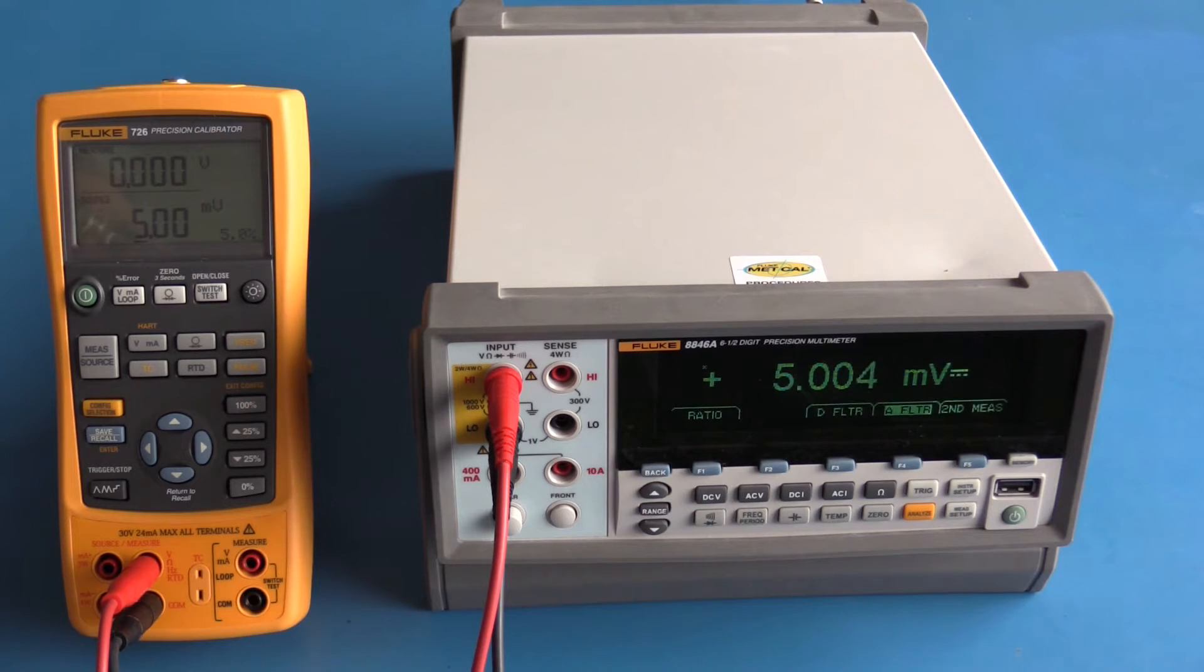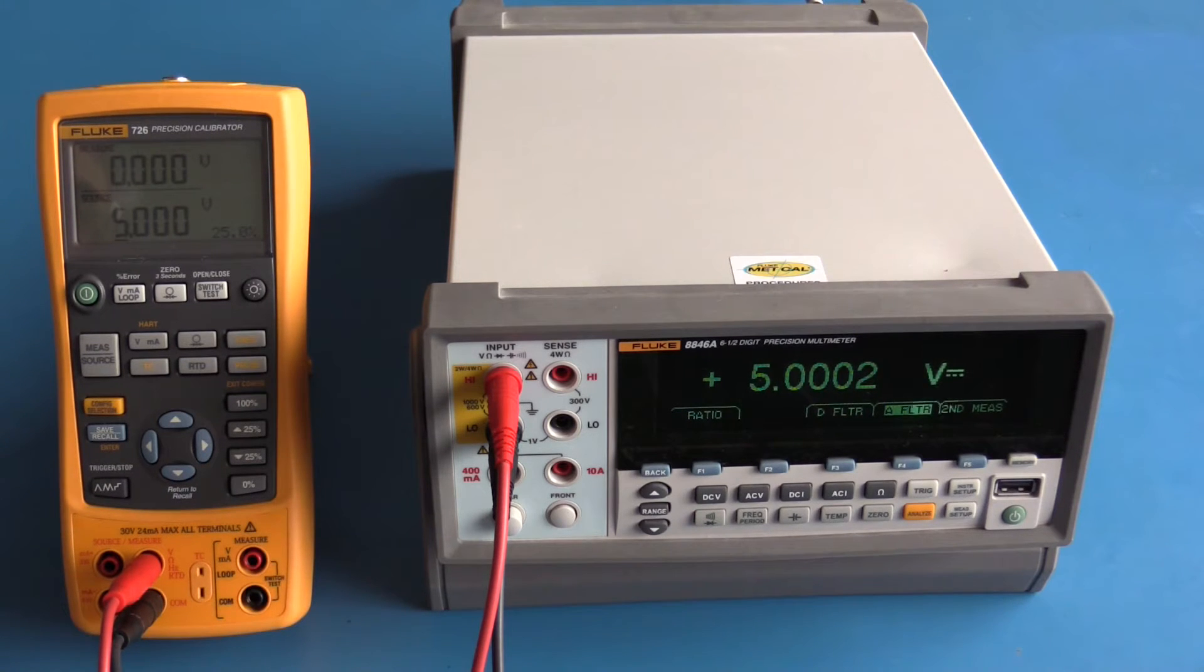I have now changed the Fluke 726 to source five volts and the Fluke 8846a is showing five volts. The Fluke 726, although it's a precision process calibrator, does not have the precision of the Fluke 8846a. We can see that the meters are in close agreement to each other, so this gives me a good level of confidence in my meters.